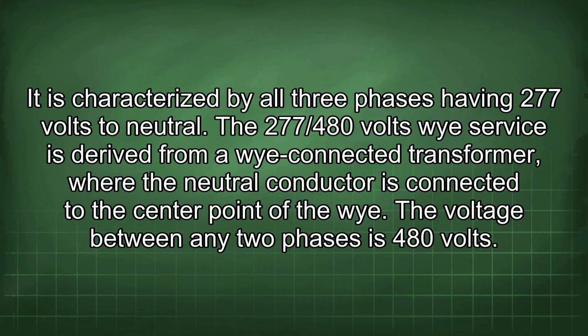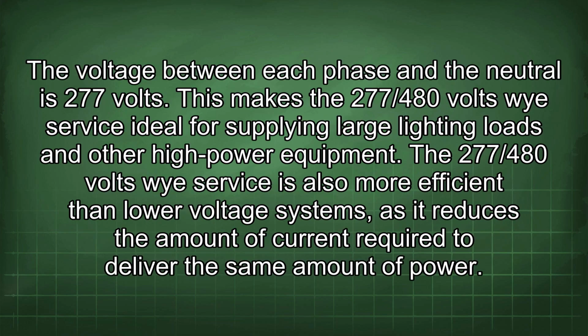The 277/480 volts Y service is derived from a Y-connected transformer, where the neutral conductor is connected to the center point of the Y. The voltage between any two phases is 480 volts. The voltage between each phase and the neutral is 277 volts.